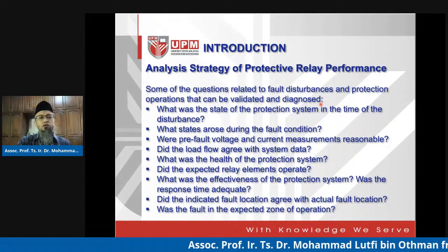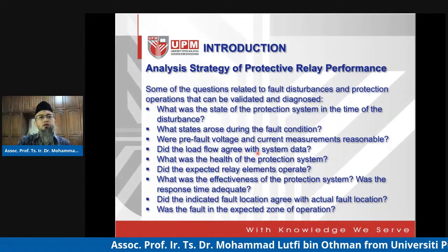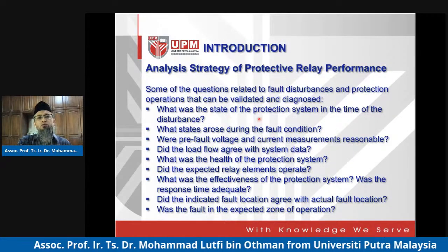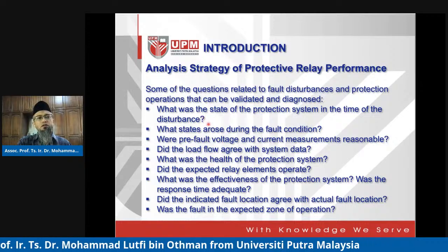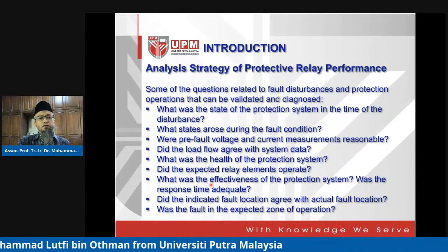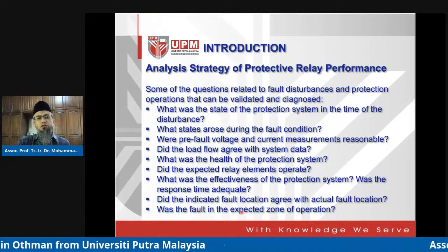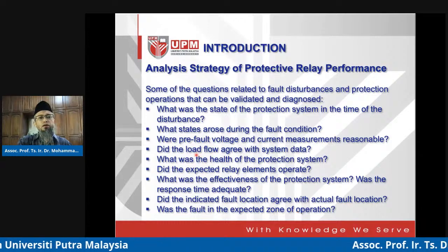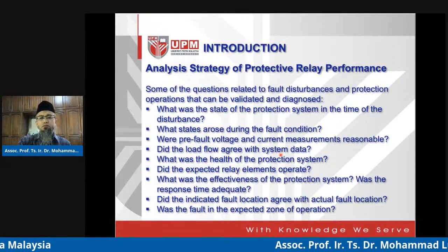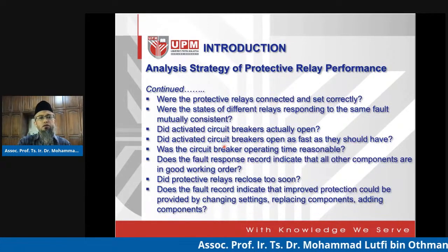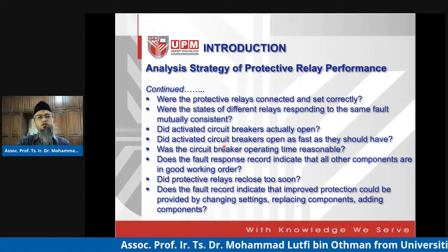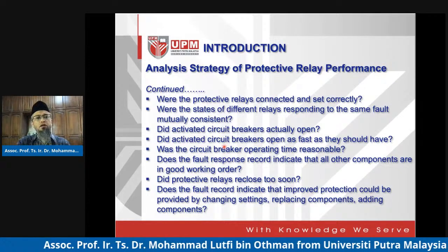I may just read one or two of them. For example, what was the state of the protection system at the time of the disturbance? Was the fault in the expected zone of operation? Did the load flow agree with the system data? And it goes on with many questions we might need to look at.